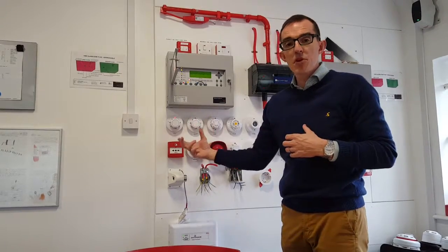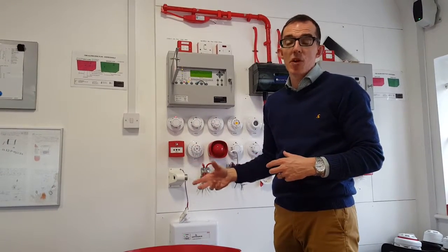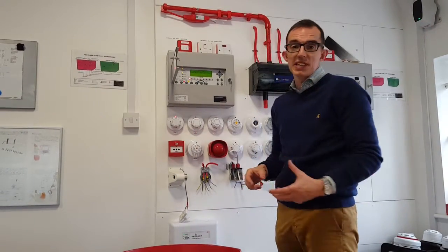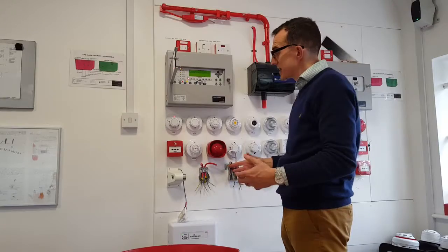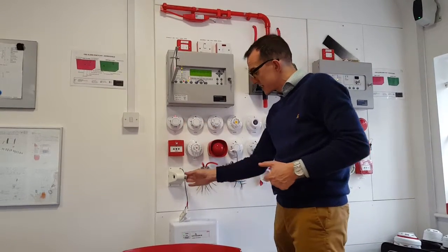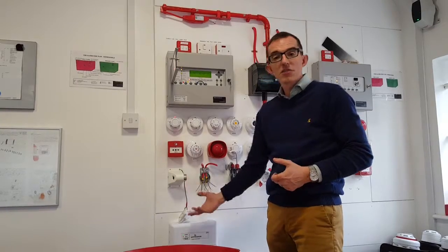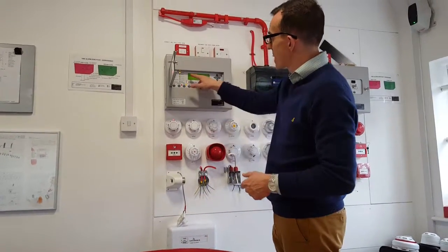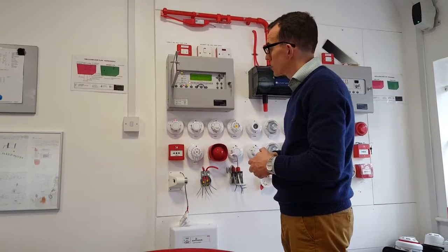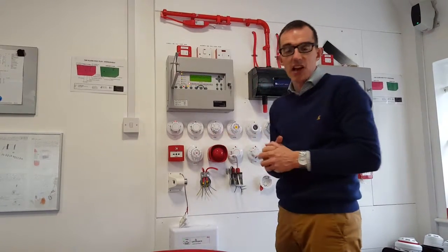So that's me proving that if there was a fire in the room and that detector was activated, then all of the things that I wanted it to do would work. So in this instance, the little light comes on, which is great. This device de-energized, releasing doors. The text came up on the screen indicating where the fire was, and we got some beacons and some flashing lights and stuff like that.